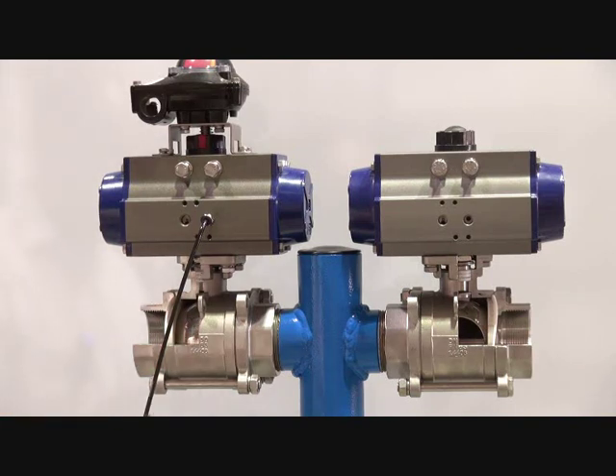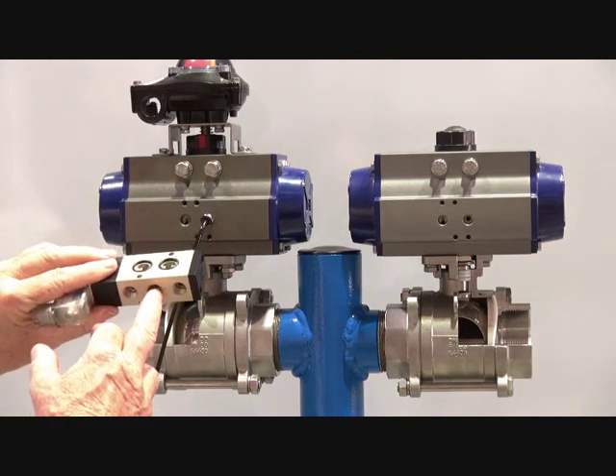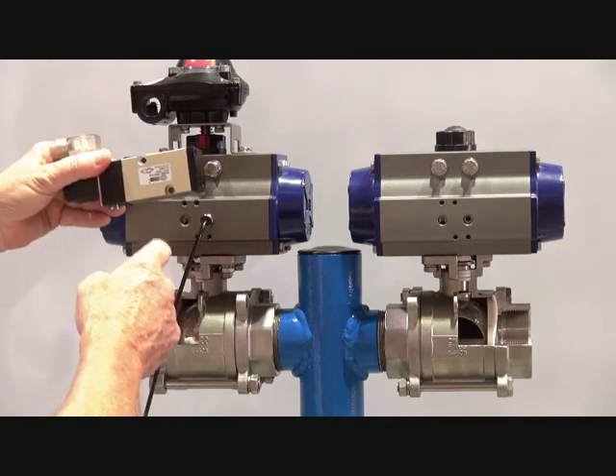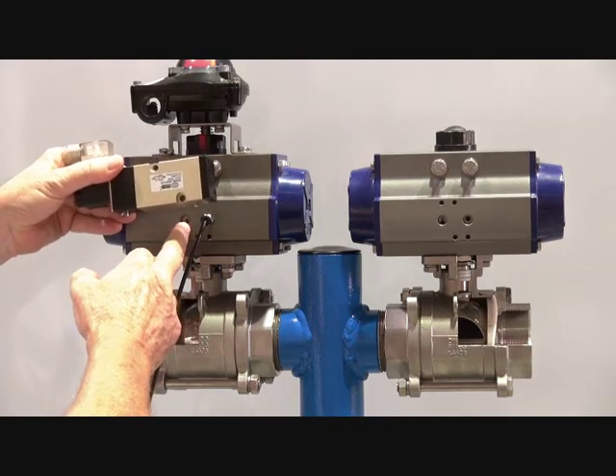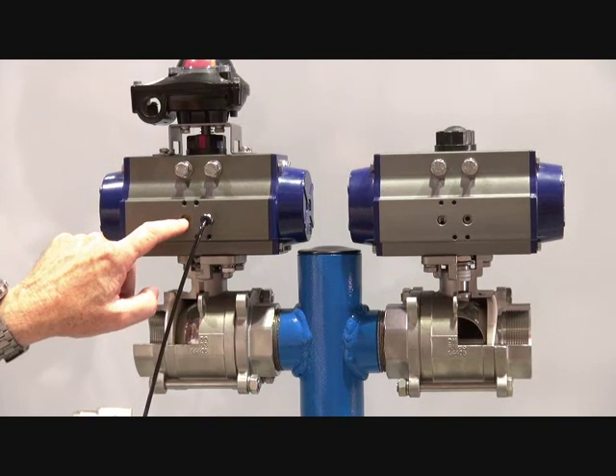We recommend to use a double solenoid on that, or a single solenoid that has a double entry. We put air in both ends even though the air is going into the spring end. It's better than sucking the air in from the outside.